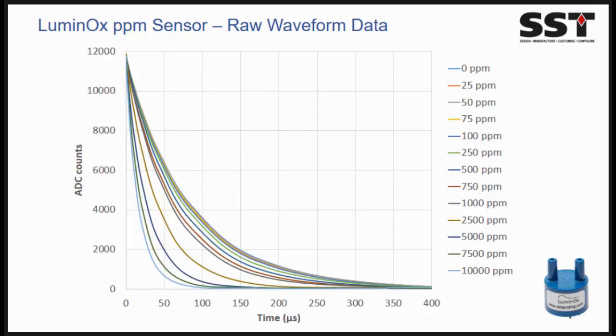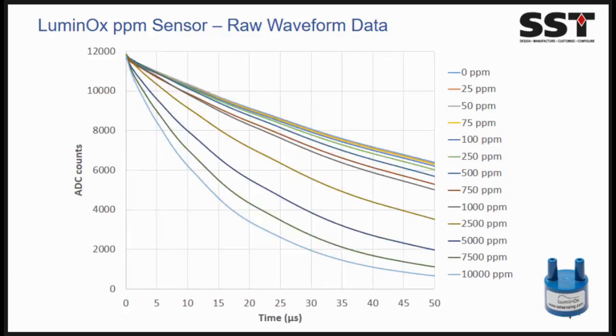So here are the raw waveforms that you probably recognised earlier. So we start the ADC counts at the same rate. So we can do this by controlling the output of the LED. So for example, at 10,000 ppm, the LED has to work a little harder to get this waveform all to start at the same place. But you can clearly see that as you increase the oxygen, the decay time gets faster and faster. And you can see this more clearly in the next image there.